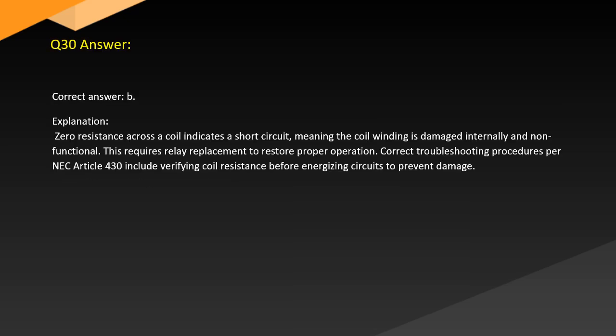Answer. Correct answer: B. Explanation. Zero resistance across a coil indicates a short circuit, meaning the coil winding is damaged internally and non-functional. This requires relay replacement to restore proper operation. Correct troubleshooting procedures per NEC Article 430 include verifying coil resistance before energizing circuits to prevent damage.